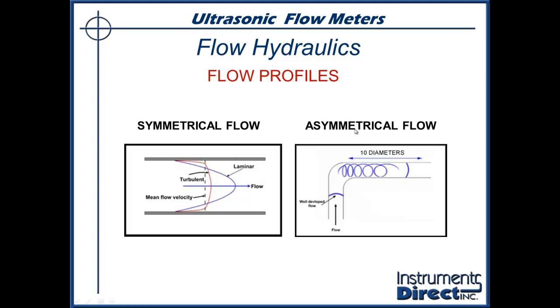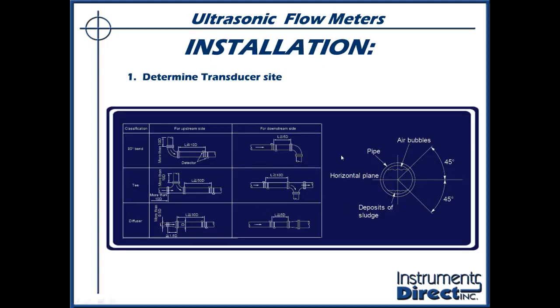The opposite is an asymmetrical flow profile. With a 90-degree elbow, the flow becomes very turbulent as it rounds the bend, and putting your flow meter right there would give poor or no results. Go downstream 10 pipe diameters to place your sensor, with another 5 on the other side. If you have too great a turbulence with a transit time meter, you won't get anything at all. For horizontal pipe, you can get solids on the bottom and aeration on the top, so the sides — 9 or 3 o'clock — may be an optimal placement for your flow sensors.